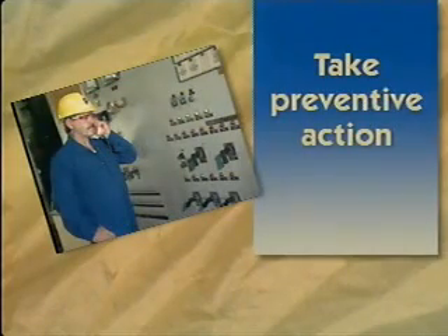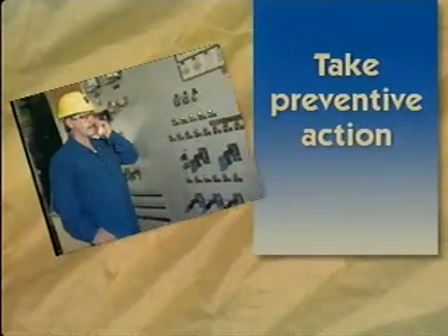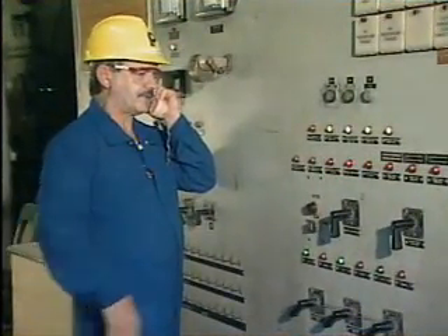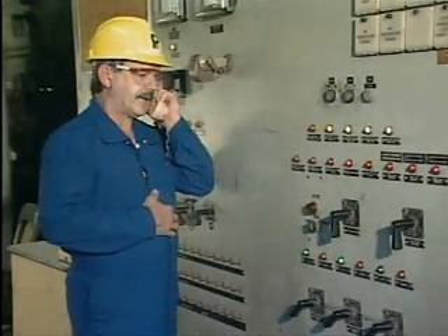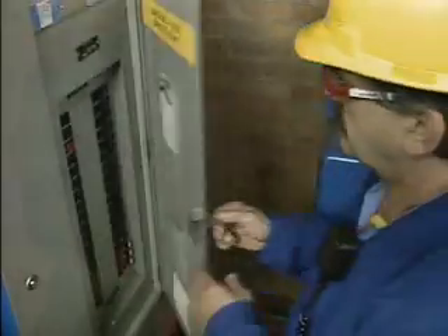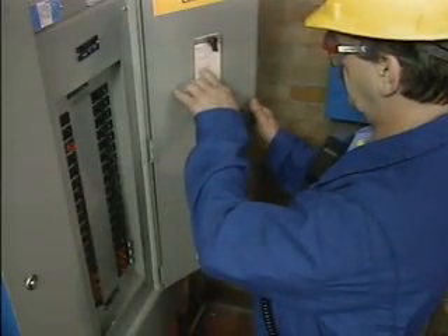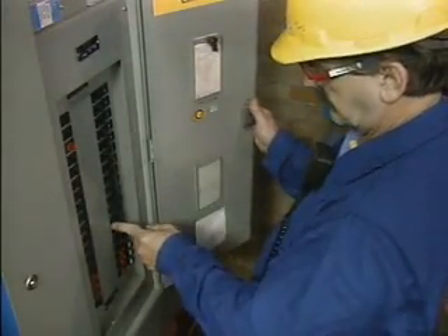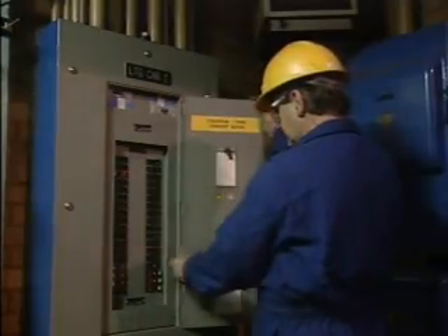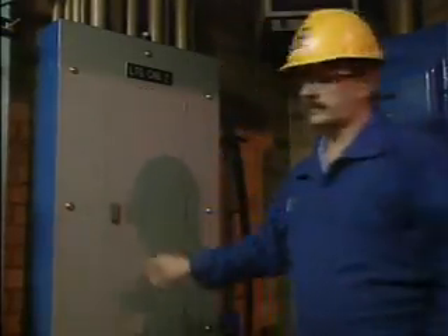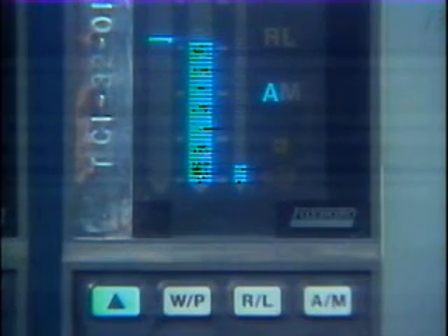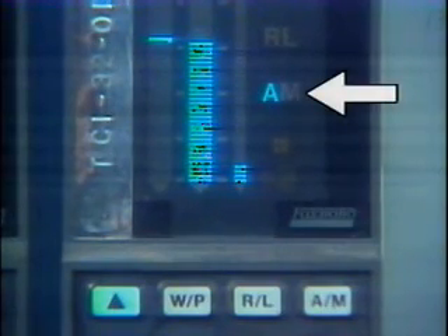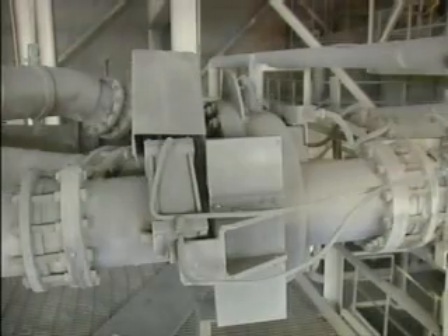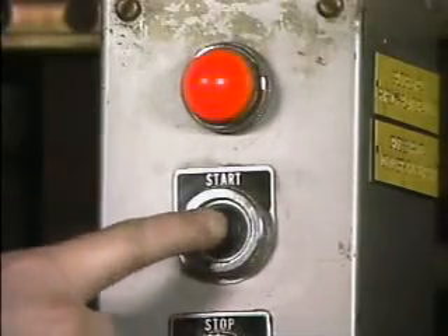Once a problem has been identified, the next step in our procedure is to take the immediate preventive action necessary to keep it from becoming worse and causing injuries or damage. It's important to note that taking preventive action is not the same thing as correcting the problem. Preventive action is a short-term action that's meant to put a circuit in a safe condition while work is performed to correct the problem. For some problems, the only way to prevent damage is to initiate an emergency shutdown. For others, you may need to switch the circuit from automatic to manual control, bypass a piece of equipment, or start up a piece of backup equipment.